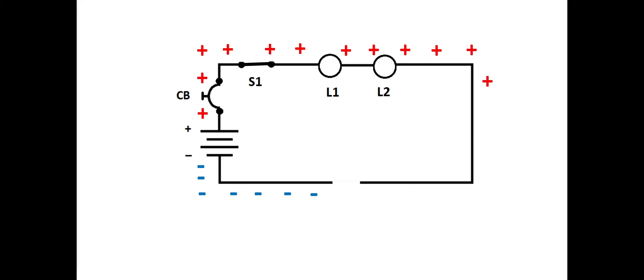If an open occurs in the circuit, the positive and negative potential will move to the open when the circuit is turned on. To troubleshoot an electric circuit with an open, you simply need to locate the positive and negative potentials. Wires are connected to terminal blocks, which allows the connection of the meter without removing insulation from the wire. Terminal blocks and terminals are identified by numbers on wiring diagrams.